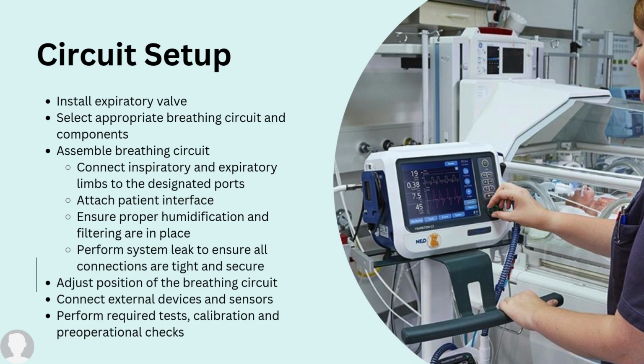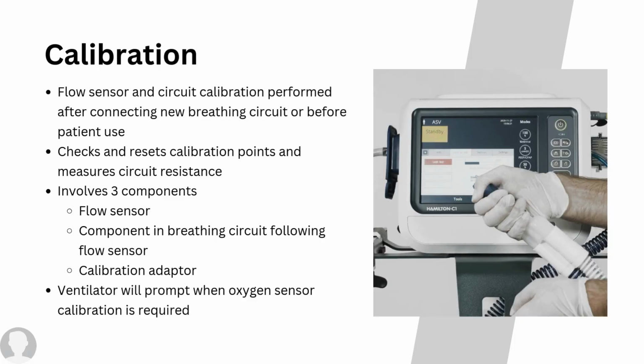We must then adjust the position of the breathing circuit, connect the external devices and sensors, and perform required tests, calibrations, and pre-operational checks. The flow sensor and circuit calibration are performed after connecting a new breathing circuit or before patient use. The purpose is to check and reset calibration points and measure circuit resistance.